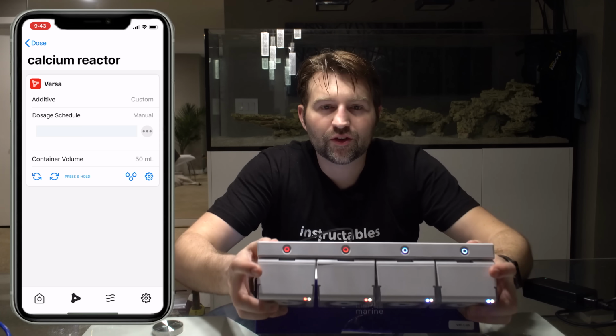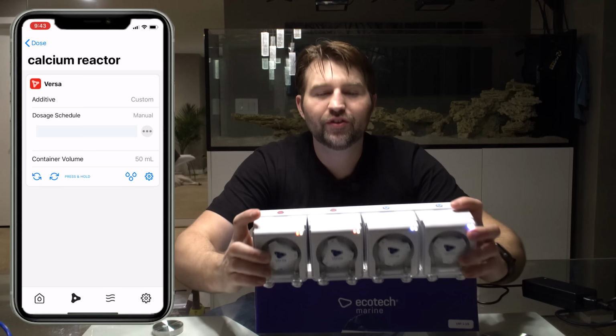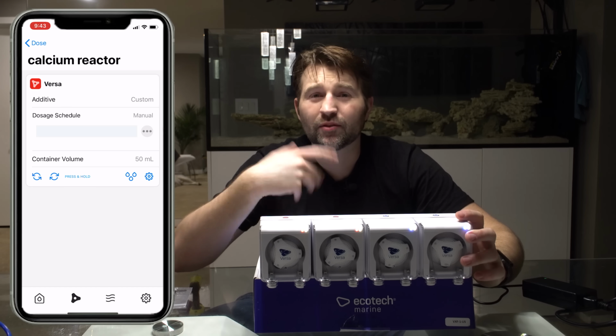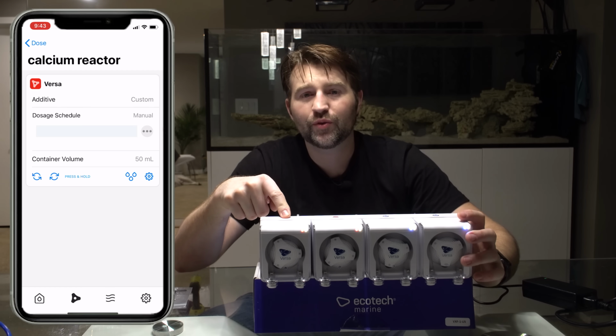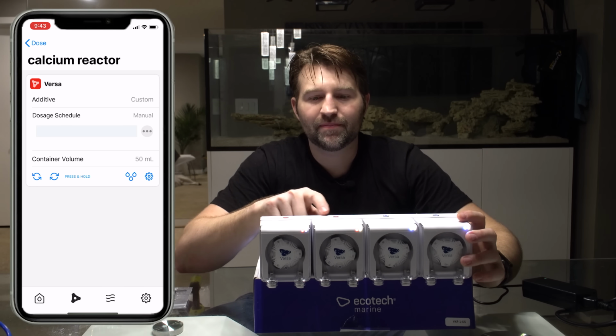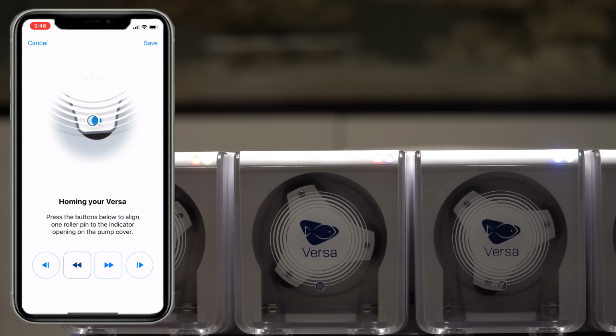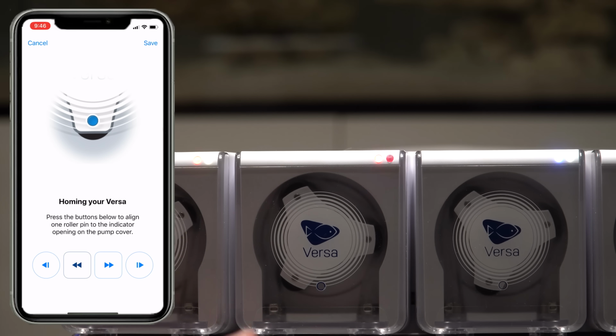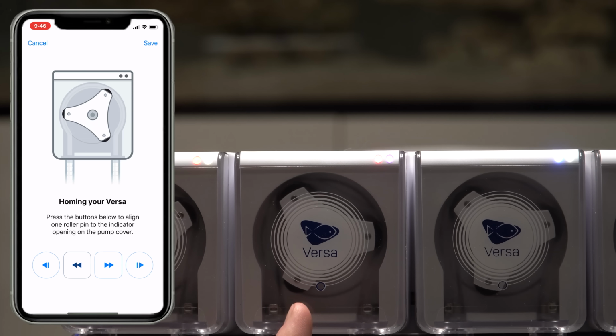If you look at the top of the doser, we also have this line of buttons, and what those do is they're for manual dosing or priming lines or pushing water through, whatever you want. So I hold this down, you can manually make the head spin. Now this is the first time I've ever seen this feature on a pump, and it's really cool. So what we're doing right now is homing the Versa. So as I'm setting the home point, you can see the pump head slowly moving as I push the button. And what we're going to do is line up that little dot with that circle.